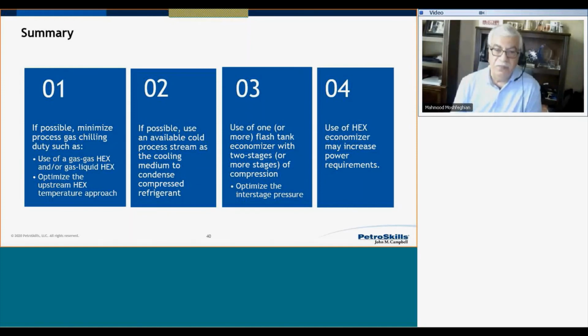So we covered lots of material. Let's review the highlights. Item 1: if possible, minimize process gas chilling duties, such as by using a gas-gas or gas-liquid exchanger upstream of your chiller. That reduces the duty requirement of the chiller by sometimes 60%, 70%. And also optimize the upstream heat exchanger temperature approach. Temperature approach has a big impact. With a lower temperature approach, your heat exchanger duty goes up and capex on the heat exchanger goes up, but the duty of your chiller goes down drastically and you save a lot of money.